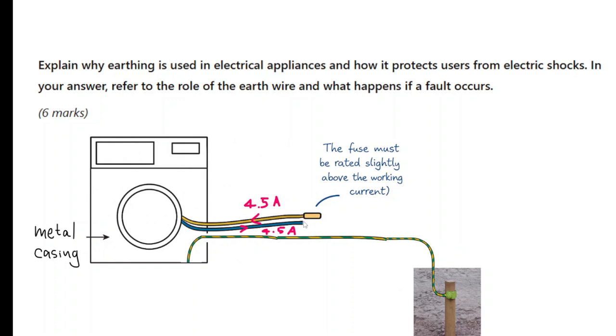The earth wire is a wire that is connected to the metal casing. So here it's connected just to the metal casing somewhere and then it is connected to the earth. It is either connected to a water pipe, metal pipe, or it is just connected to a metal pole and driven into the ground. So it gives a very low resistant path to the ground. Now under normal conditions, when there is no fault, there's no current through the earth wire. The earth wire is just there, that's a safety feature.